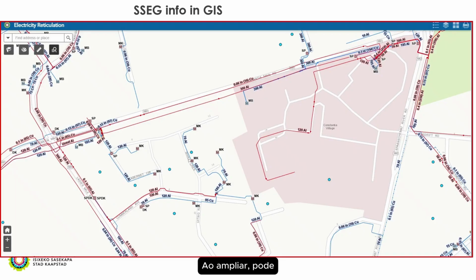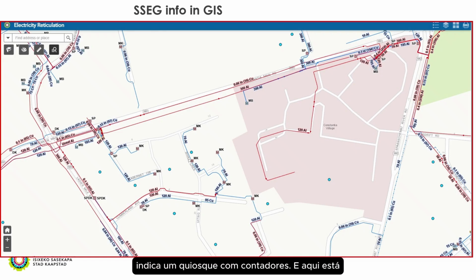Zooming into that, you can see here the blue dots. Those represent the SSEG installations. And then you see the red and blue lines. Those are the electrical network. The red line is the MV network, and the blue line is the LV network. The MK there is the meter kiosk. And this is how all of these SSEG installations tie up into the electrical network, where we can ensure, in terms of NRS 097-2-3, that the 75% of the maximum export capacity of the transformer rating is not exceeded.